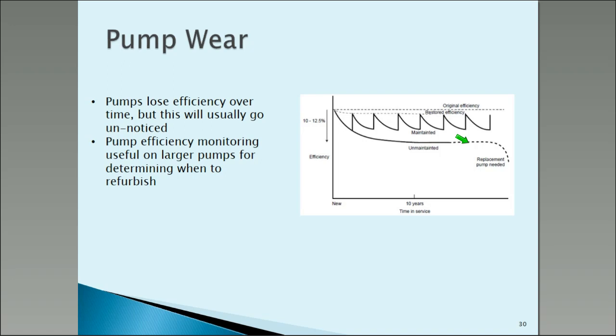And finally, we're going to look at pump wear. Unlike motors, pumps do wear out — especially if there's something like grit around, as at steelworks. The efficiency will gradually deteriorate. You can refurbish them and get nearly back to where you were to begin with, but the efficiency eventually falls off again. It's a matter of how often you want to refurbish. To be honest, for a lot of small pumps, you'd just throw them out or put on a new pump.